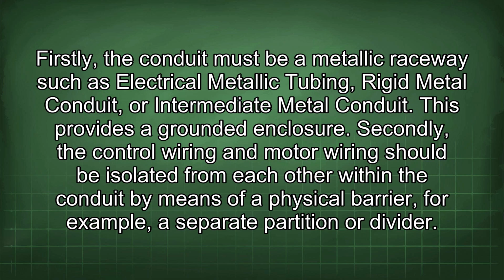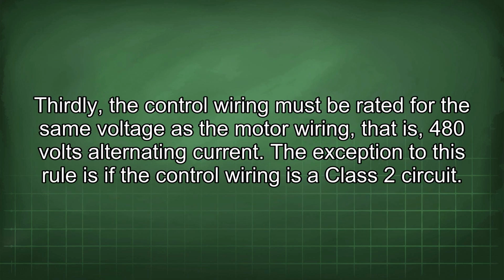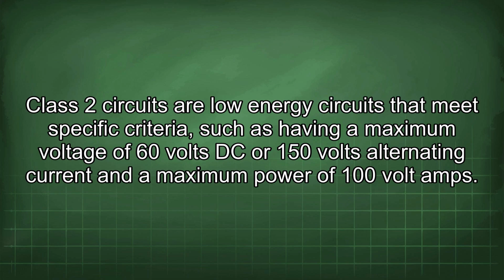Secondly, the control wiring and motor wiring should be isolated from each other within the conduit by means of a physical barrier, for example, a separate partition or divider. Thirdly, the control wiring must be rated for the same voltage as the motor wiring, that is, 480 volts alternating current. The exception to this rule is if the control wiring is a Class 2 circuit. Class 2 circuits are low-energy circuits that meet specific criteria, such as having a maximum voltage of 60 volts DC or 150 volts alternating current and a maximum power of 100 volt-amps.